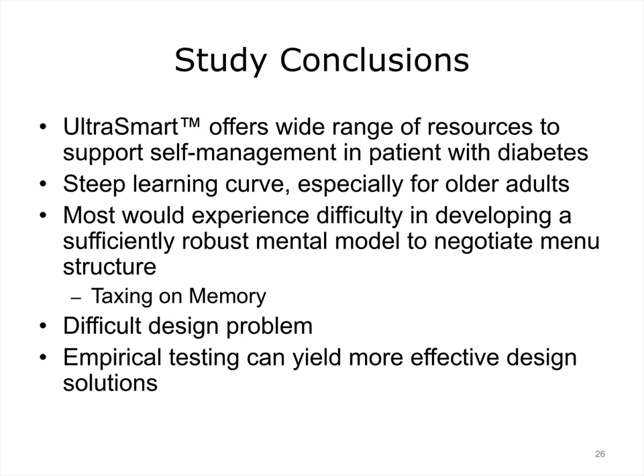In conclusion, the glucose meter offers a wide range of resources to support self-management in patients with diabetes. However, mastery is associated with a steep learning curve, especially for older adults. Most users would experience difficulty in developing a sufficiently robust mental model to negotiate the complex menu structure. We have to acknowledge that this is a difficult design problem given the size of the screen and the limited interaction possibilities — for example, there is no keyboard or mouse. There is no question that usability testing can be used to glean more effective design solutions and weed out suboptimal design dimensions.